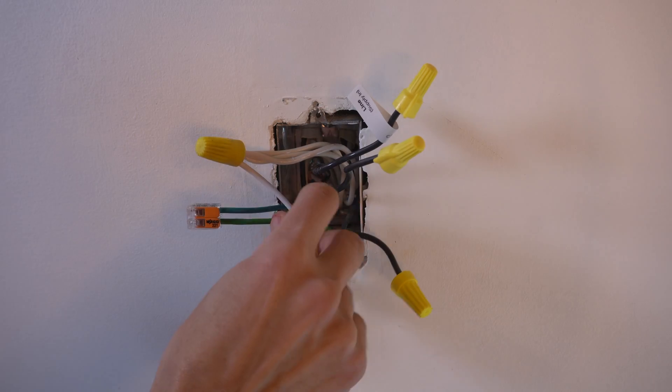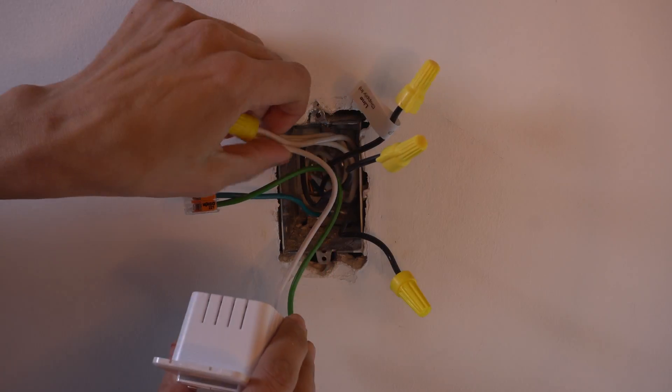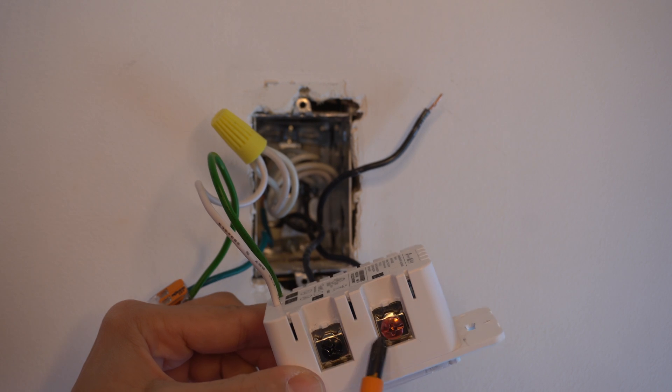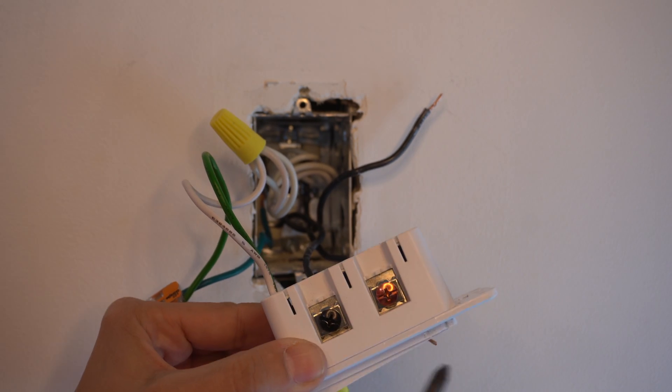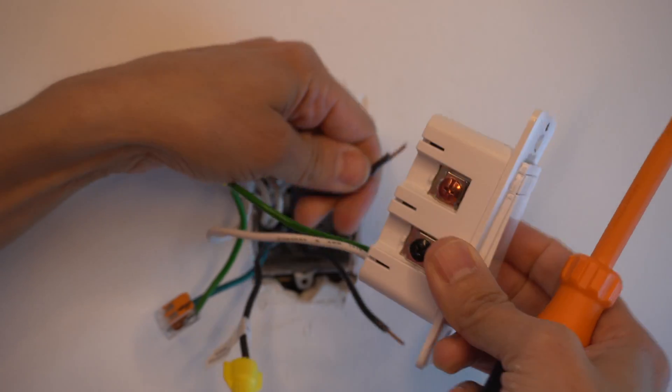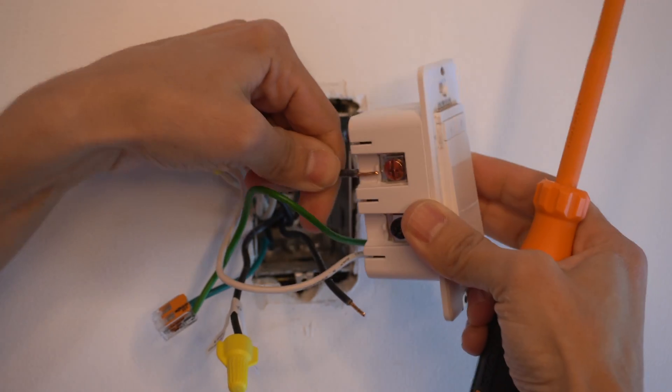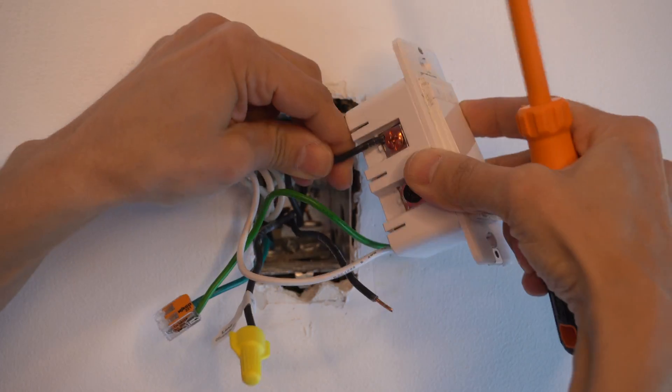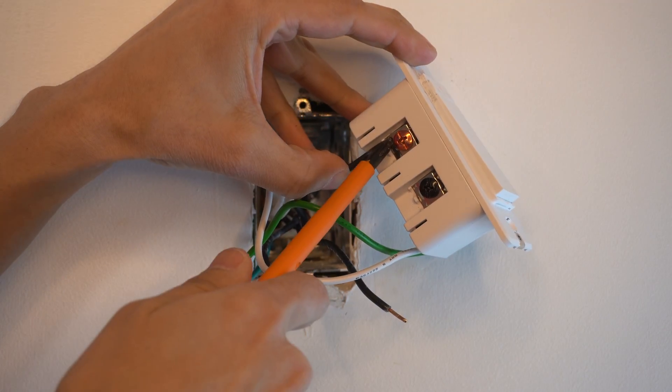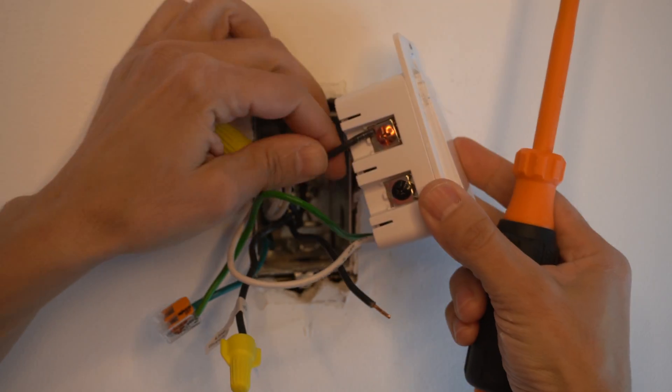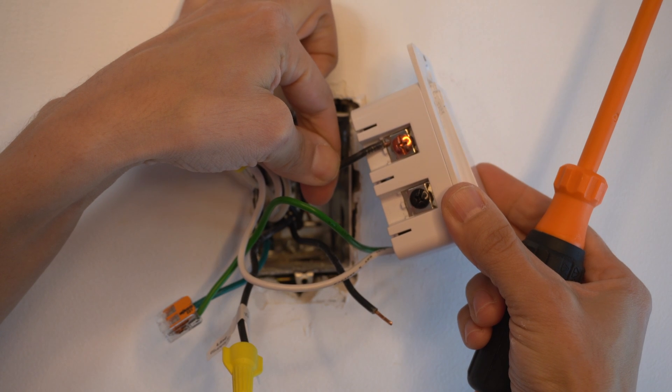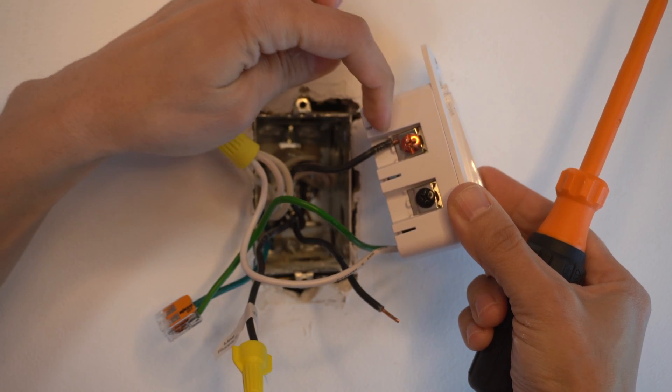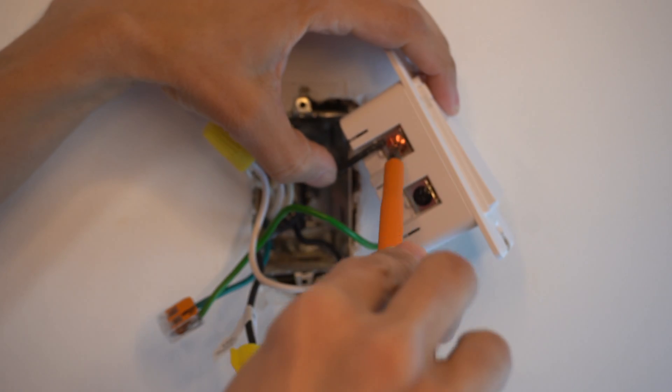Looking at the screw terminals here on the side, I'm going to start with my load wire, which is the red screw terminal. I'm just going to insert it into the side behind this little clamp. We want all the insulation covered. If you were to install it like that, that would be incorrect. We do not want to have any exposed copper wire there. Push it in - that's what we're looking for - and then we'll just secure that up.